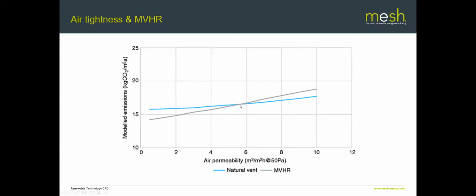is around about five and a little bit meters cubed per hour per meter squared at 50 pascals, which incidentally you'll note is around about the same value which building regulations Approved Document F now says is where natural ventilation is no longer suitable. So those sit quite nicely, but it's just worth bearing in mind that if you've got a leaky old building, it may well not be a benefit to actually put MVHR in, because it will cost you more to run than the energy it will save, and you'd actually be better off either spending a bit more time trying to tighten the building up if you want to use an MVHR system, or maybe considering a natural ventilation system instead.